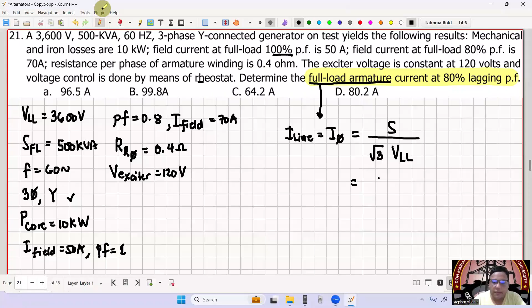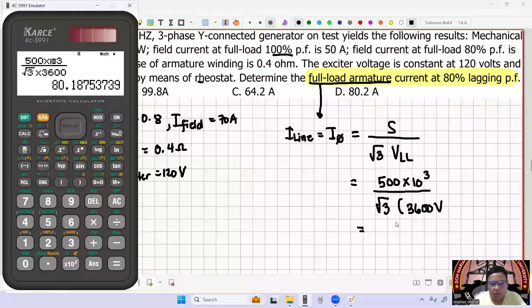So this becomes 500 kilo over square root of 3 multiplied by 3,600. So I line or I per phase is equal to 500 times 10 raised to 3 all over square root of 3 multiplied by 3,600, which equals 80.2 amperes.